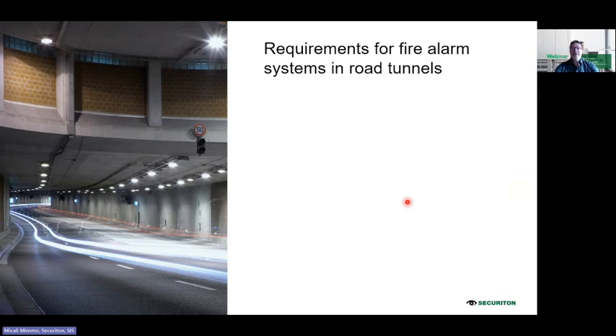Well, then let's see the requirements for a fire alarm system in road tunnels. This is a really special application. We are not talking about an application in a hotel or a commercial building. This application has a lot of environmental conditions, and the system must be prepared to work under such extreme conditions. One of those is the emission of diesel exhaust particles. Of course, here we have a lot of cars and trucks driving in the tunnel every day, and there is quite a high concentration of those kinds of particles. Then humidity is also a topic. Depending on the location of the tunnel, we may have higher or lower humidity during the day and in the night.